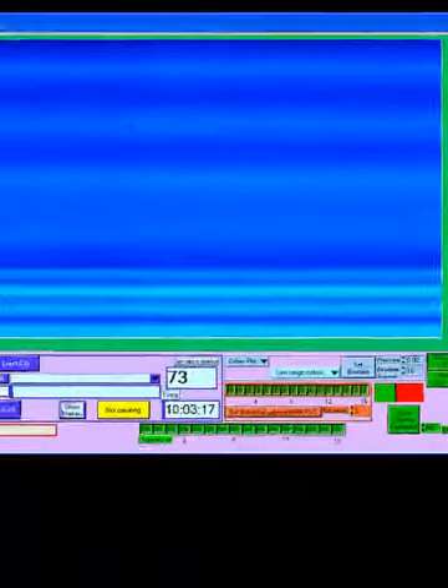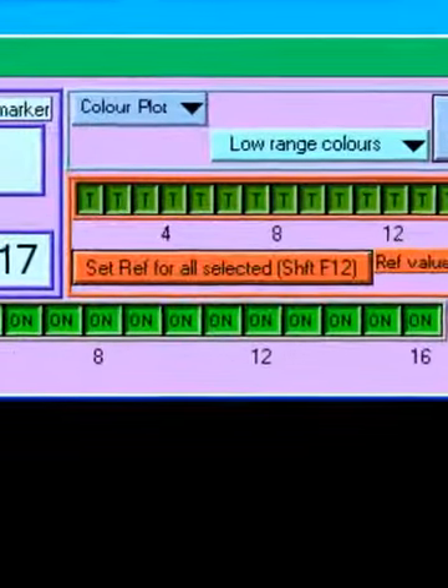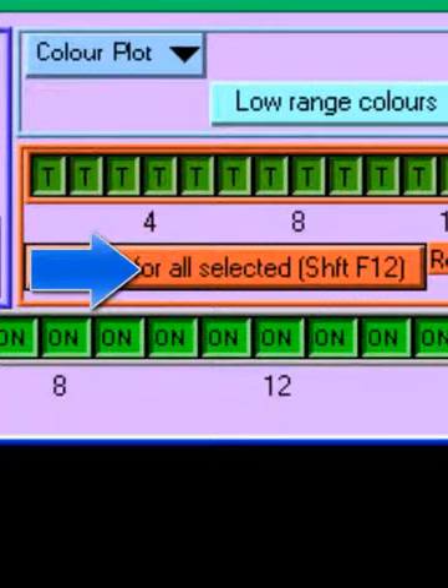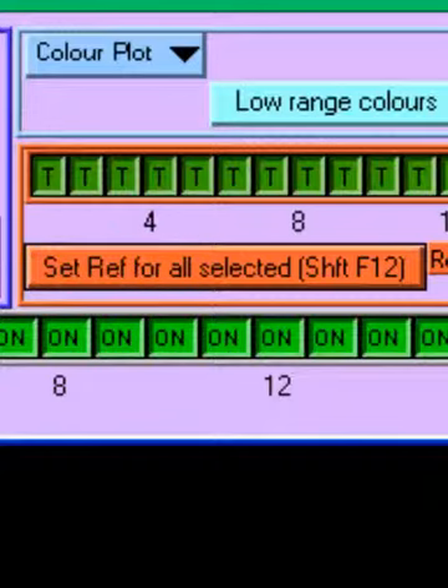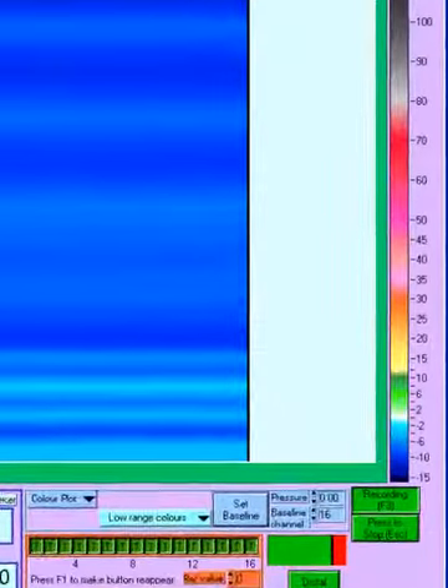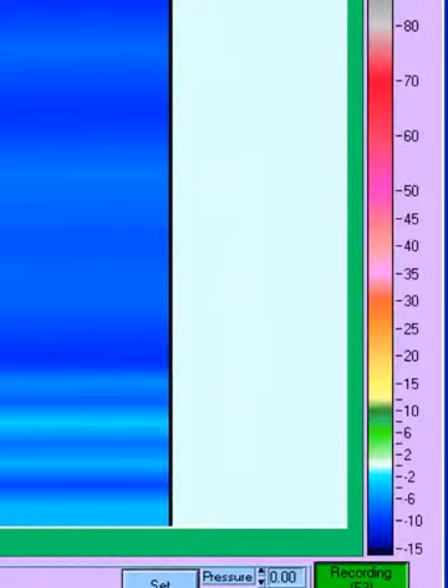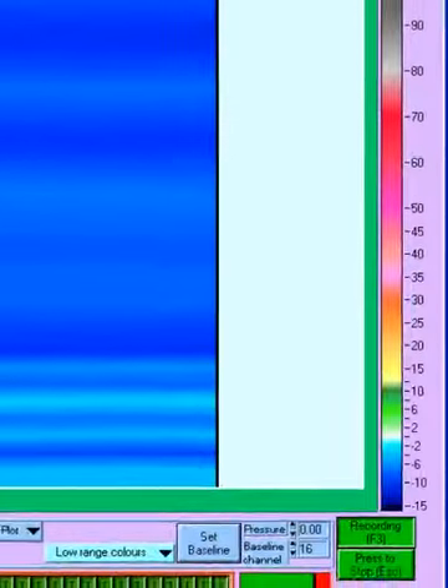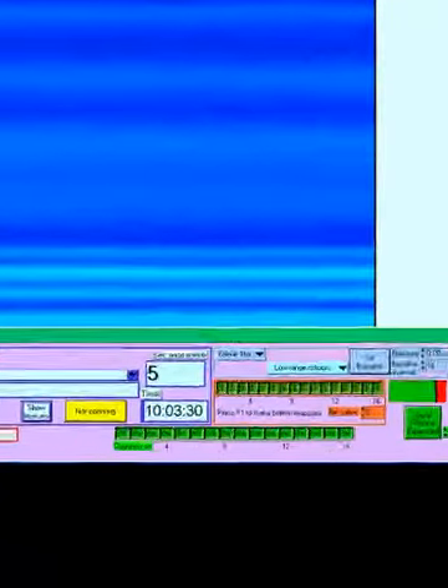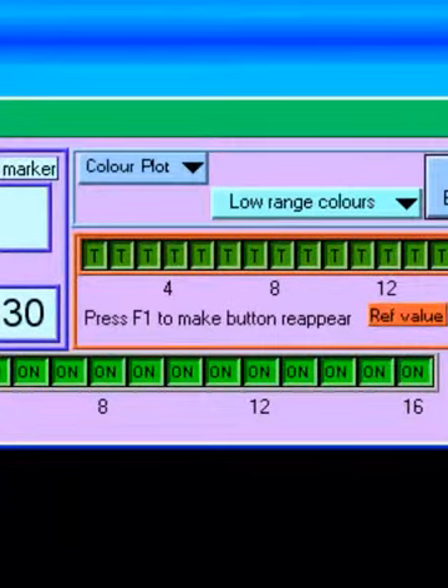When it is clear that the pressures are stable, press on the tan-coloured Set Reference Value for All Channels button. This sets the instantaneous pressures in all channels to 0 and is required to remove the pressure offsets due to perfusion of fluid through the catheter. If this step is not completed, the data recorded will not be accurate. The screen should go white to the right of the marker and remain white, perhaps with very light green or blue horizontal stripes, which indicate a minor degree of drift in the perfusion pressures. If there is significant drift, flush the catheter and reset the atmospheric reference pressures. You will need to press F1 to make the button reappear before you can press it again.